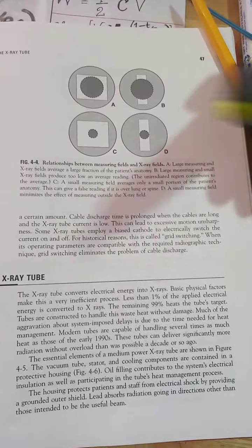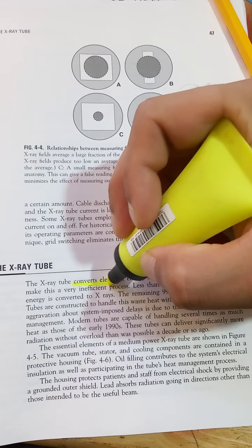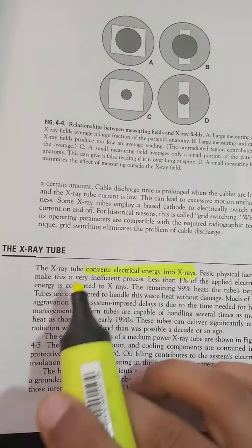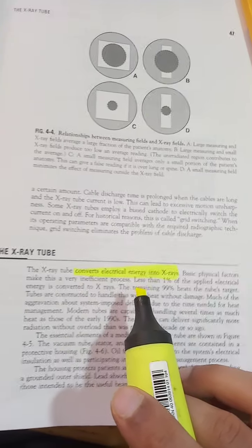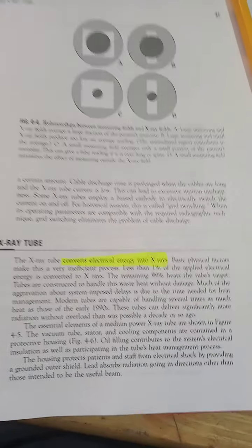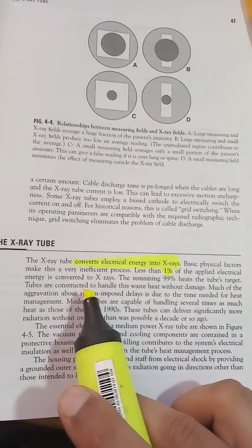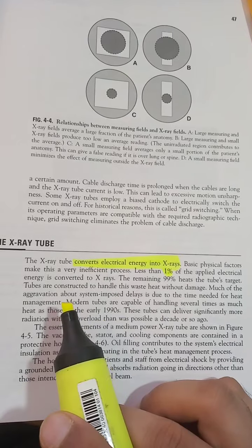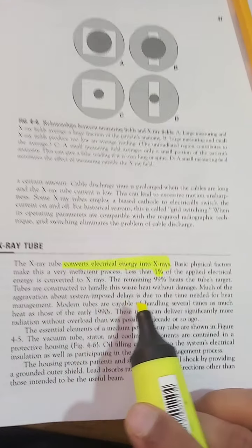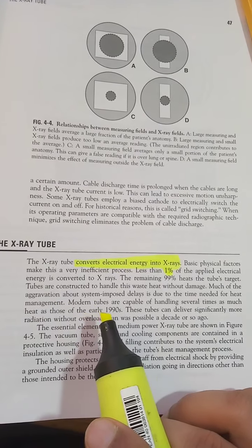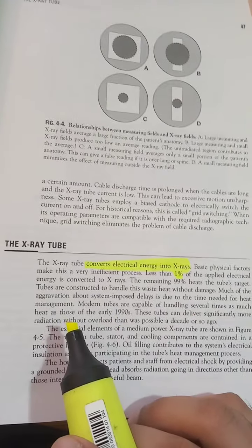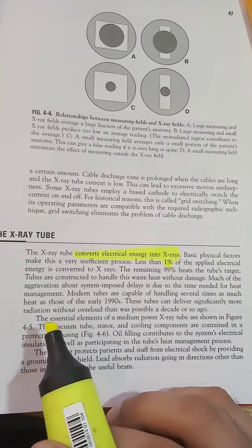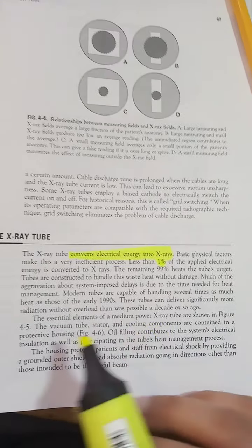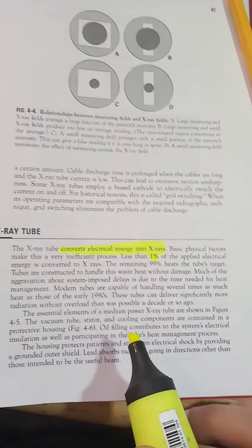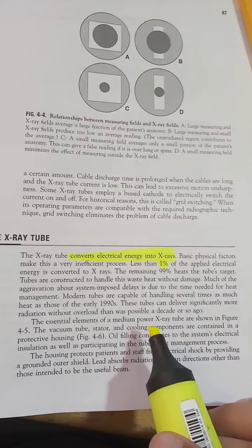The X-ray tube converts electrical energy into X-rays. Okay, basic physical factors make this a very inefficient process, very inefficient, like the incandescent light bulb. Less than 1% of the electrical energy is converted to X-rays. The remaining is heat, and tubes are constructed to handle this waste heat without damage. So much of the aggravation about system-imposed delays is due to time needed for heat management. Modern tubes are capable of handling several times as much heat as those of the early 90s. These tubes can deliver significantly more radiation without overload. This was not possible a decade or so ago.